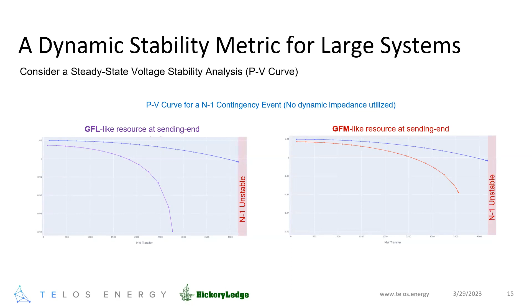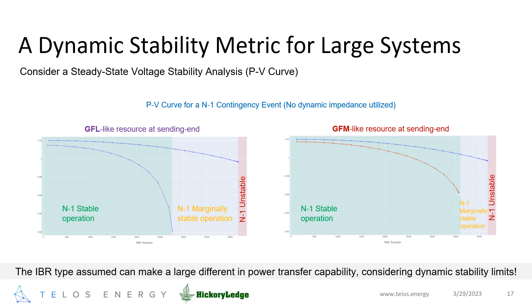Beyond the idealized curve, you are certainly unstable. Within the bounds of the curve where the dynamic impedance is applied, you have stable operation. Somewhere in between, you have some marginal stability, where frankly this method just doesn't have that fine a point. But what you can see is there is a substantial difference in how much power you're able to transfer across the system, depending on how your resource is behaving and how well it is controlling its terminal voltages. These differences can be quite substantial, and the assumptions you're making about those resources have a big effect on power transfer and its stability.